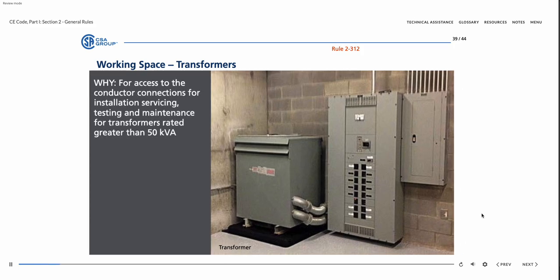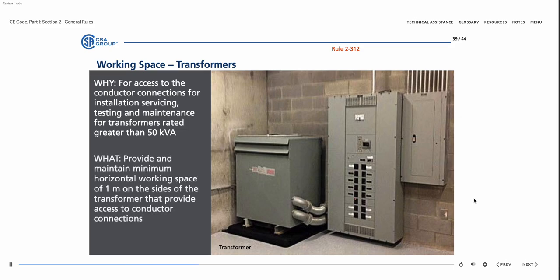To provide access to the conductor connections for installation, servicing, testing, and maintenance for transformers rated greater than 50 kVA, a minimum horizontal working space of 1 meter is to be provided and maintained on the sides of the transformer that provide access to conductor connections. This working space is not in addition to the space required by Rule 26-242.